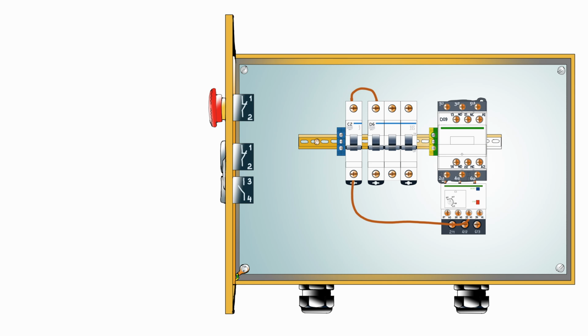So we draw a connection from 96 on the overload relay to 1 on the e-stop button, and then from 2 on the e-stop button we go to 1 on the stop button, and then from 2 on the stop button we go to 3 on the start button. So 3 on the start button is the same connection with 13 on the auxiliary contact.